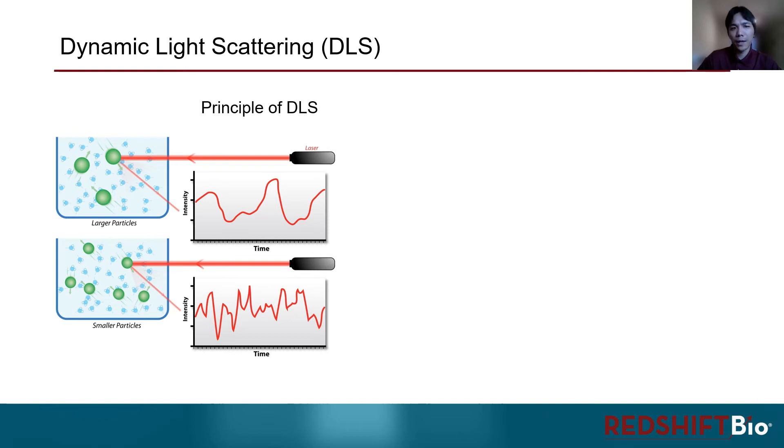So how does DLS work? In a typical DLS measurement, particles in a solution are exposed to a laser. Then the scattered light after hitting the particles is measured directly by a detector. The intensity of the light being scattered will change over time as the particles continue to diffuse. The speed of these intensity fluctuations depends on the diffusion rate of the particles.